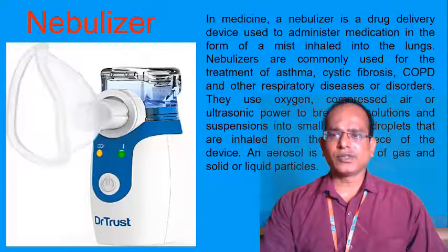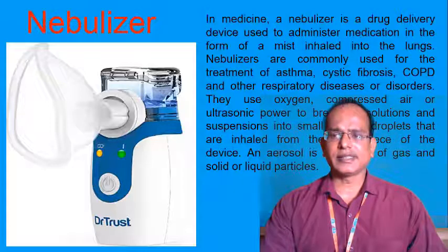Nebulizers are commonly used for the treatment of asthma, cystic fibrosis, COPD, that is chronic obstructive pulmonary disease, and other respiratory diseases or disorders. They use oxygen, compressed air or ultrasonic power to break up solutions and suspensions into small aerosol droplets that are inhaled from the mouthpiece of a device.